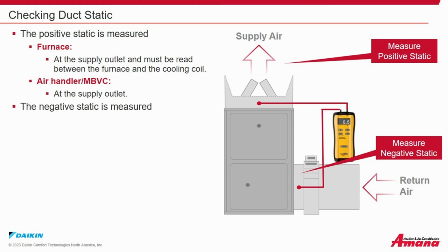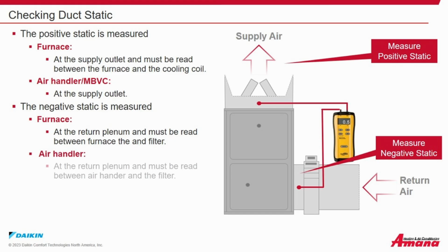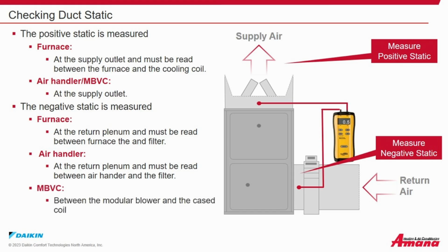The negative static is measured on a furnace at the plenum and must be read between the furnace and the filter. On an air handler at the return plenum and must be read between the air handler and the filter. On an MBVC, between the modular blower and the cased coil. Caution: when making the penetrations for your test probes, be careful not to damage the components within the cased coil.